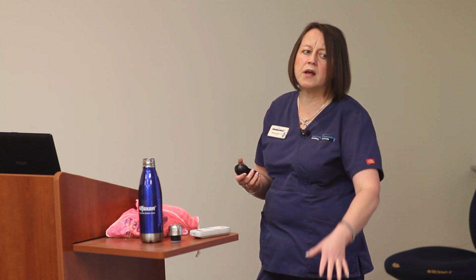Harry Latshaw wrote a little article on that one time. The inside of that is very alkaline. I don't think it's very hospitable to microorganisms, so that is why we don't often have to disinfect the inside of the anesthetic machine. And most of the time we're not even doing a lot with these hoses. These bags, I will tell you, we probably should clean them more often. We use the 5 liter one time, it hangs on the wall for 6 months and gets a hole around the neck. I know we hardly ever use them, but they get holes in them all the time.